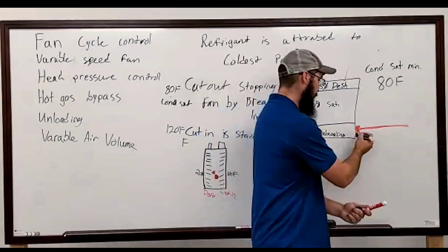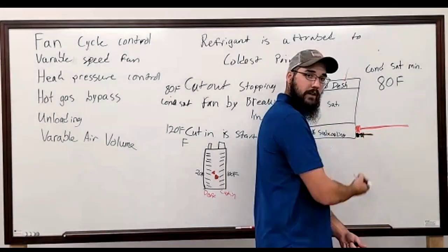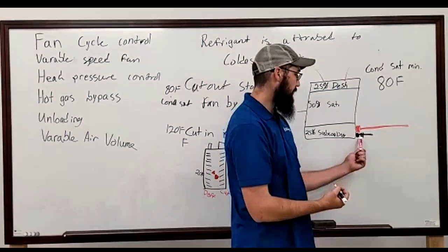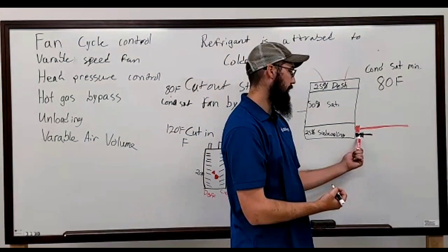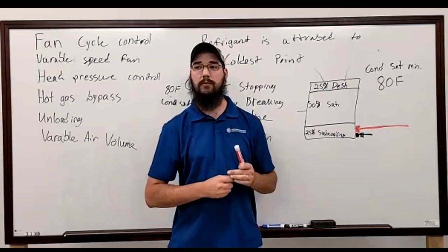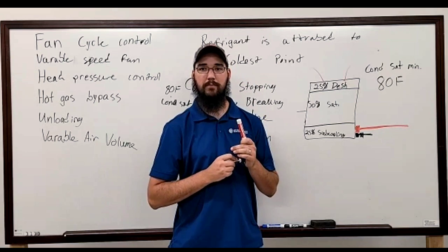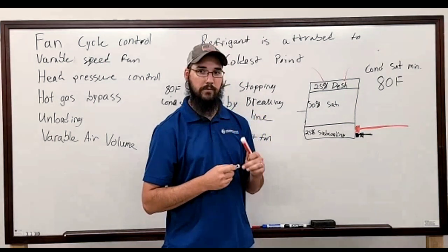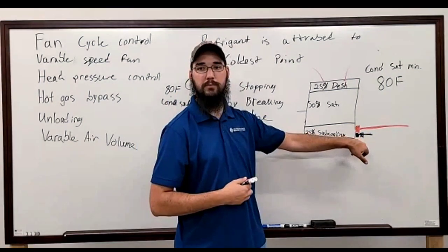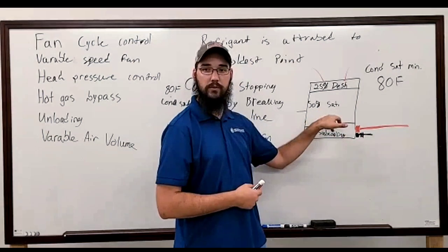The problem is, because this is where we would always hook up for fan cycle control, off of that liquid line tap, this now becomes two-phase in the heat mode of that system, not liquid line. Are you following me? Exactly. In heat mode, this port becomes a low-pressure port, and it kills the fan and freezes the coil.